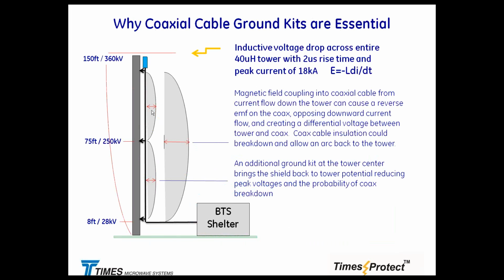People ask why we have to take a perfectly good coax cable, strip the insulation, apply the grounding kit, and tie it to the tower. The reason is the differential inductive voltage drop on the tower, due to its inductance, and on the coaxial grounding kits. We don't want to burn insulation. We don't want to arc from cable to cable, or from cable to tower or cable tray. So the reason we are butchering perfectly good coaxial cable is just to bring the inductive voltage drop across the tower closer to the inductive voltage drop across the cable.